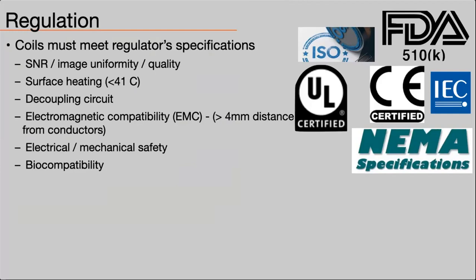So SNR, image uniformity and image quality, surface heating - which, for example, you have to maintain less than 41 degrees at every place that touches the patient. The decoupling circuit you're using, any electromagnetic compatibility - for example, you have to have a spacing of at least 4 millimeters distance from any conductor on the coil.